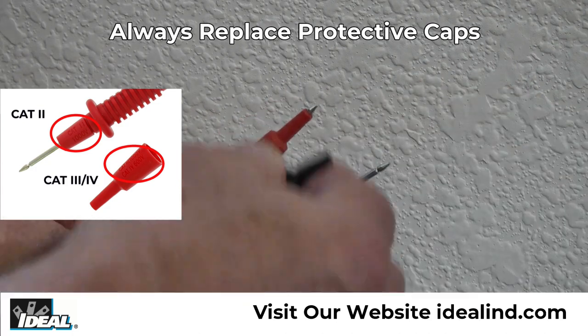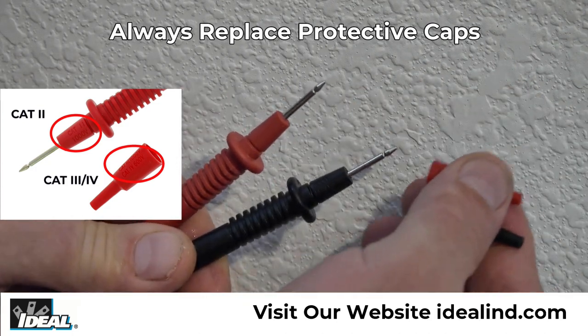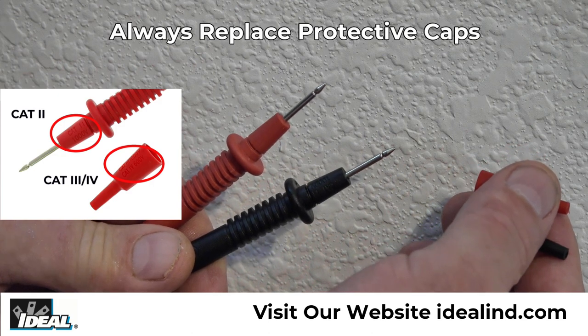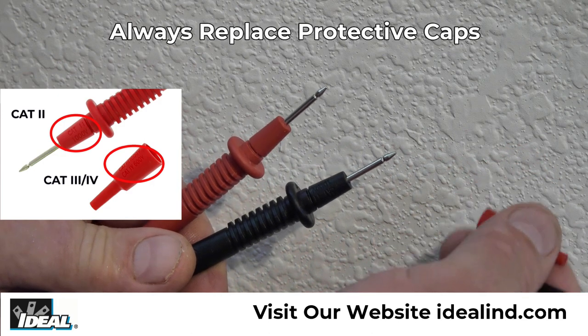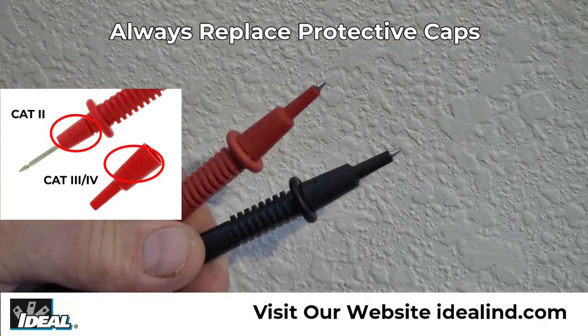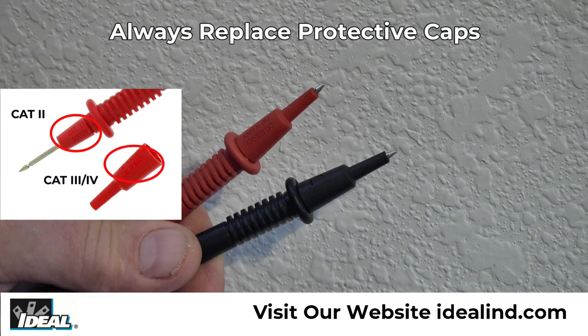Note that the CAT3 or CAT4 safety rating of the tester is lowered to a CAT2 rating when the protective caps are removed from the test leads. Always replace them after testing a standard outlet to reduce the chances of inadvertently shorting two conductors with exposed metal tips.